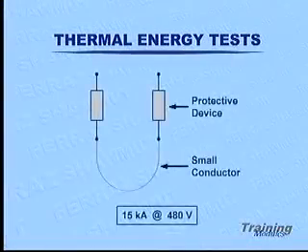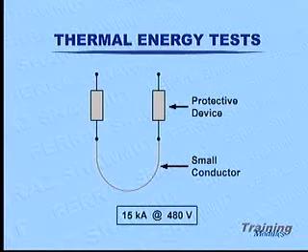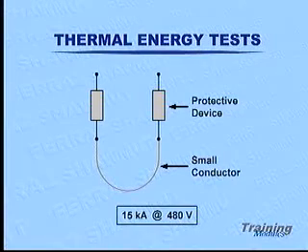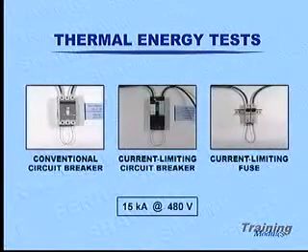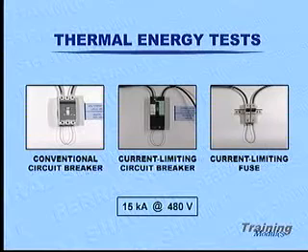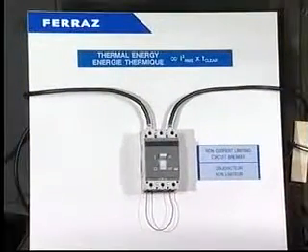For this set of comparative tests, we have a short piece of low ampacity conductor exposed to an available fault current of 15,000 amperes, 480 volts. The three protective devices, all rated 25 amperes, are conventional circuit breaker, current limiting breaker, and current limiting fuses. The first test shows the non-current limiting breaker.